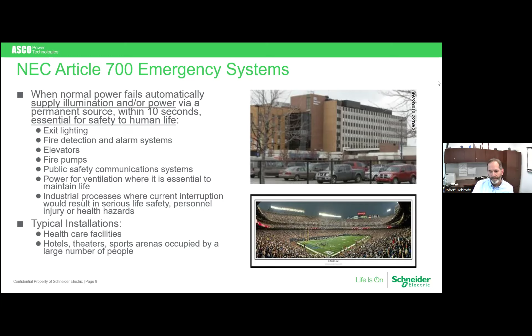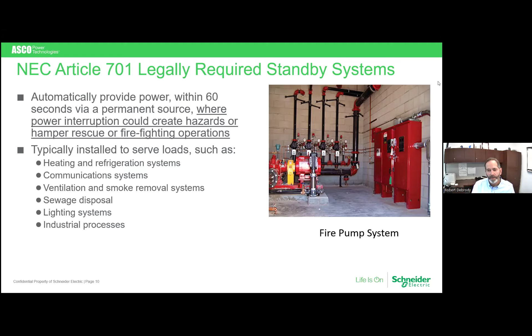The next one down is legally required standby systems, where interruption of power could create a hazard or hamper firefighting or rescue operations. Here they give you a bit more time — on emergency systems you only had 10 seconds to switch to backup power, but here you're given 60 seconds because it's not quite so critical. This powers things like sewage disposal, ventilation, smoke removal systems, and communication systems.